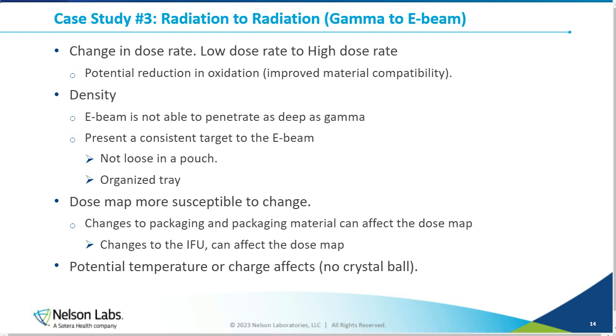So that is going to potentially reduce the oxidation and improve materials compatibility for the product. However, that's really not the only consideration that we need to have from a materials compatibility standpoint. So the ISO standard does give some guidance that a product qualified at a low dose rate, such as gamma or X-ray, will typically require minimum qualification to demonstrate material compatibility at a high dose rate. However, that's considering all things being equal. So just because there's a dose rate difference doesn't mean I'm not going to see a difference also in my dose range, again, that we demonstrated earlier. And that increase in dose is going to affect materials compatibility, and we need to be mindful of that.